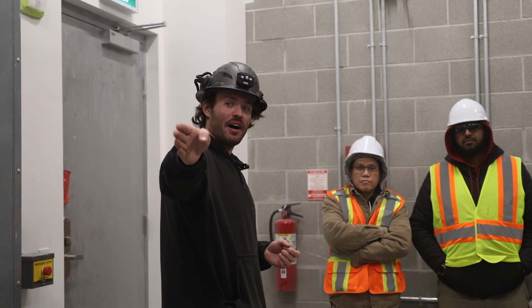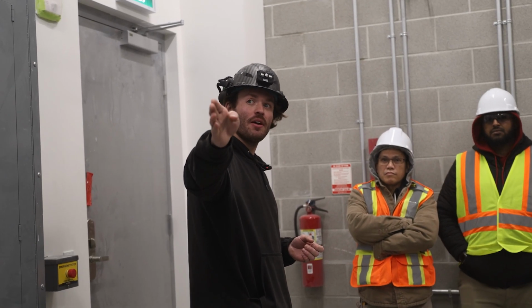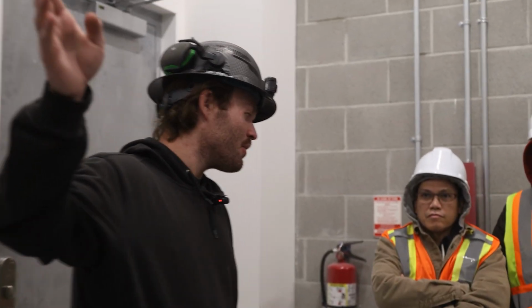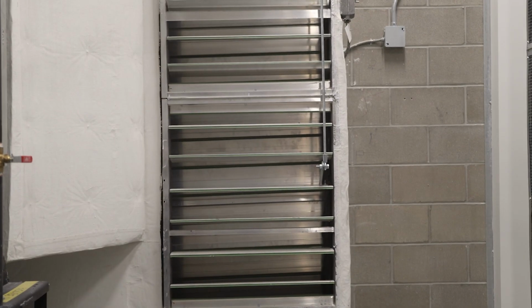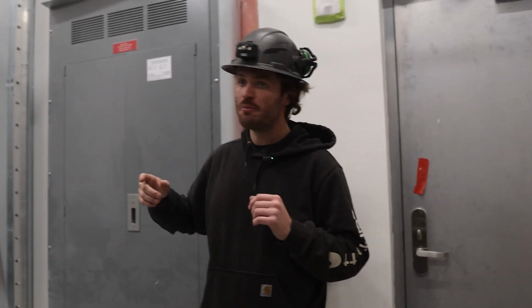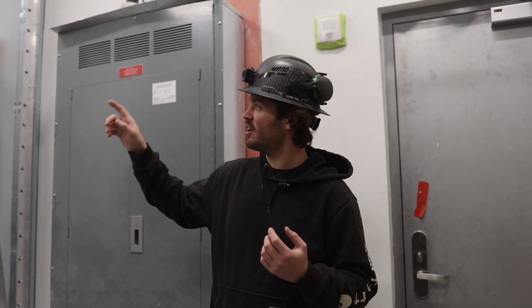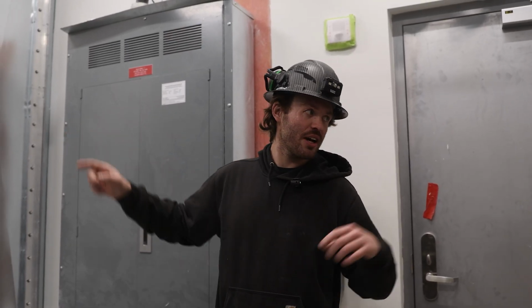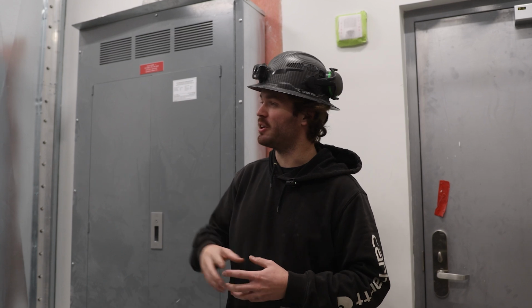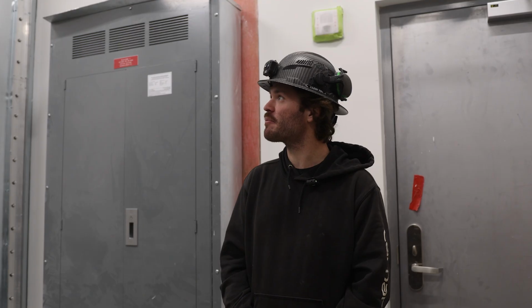The louvers behind the camera guy there, those ones are our recirc louvers. Those will always be open. We need a place for the air to be pushed by the radiator, by our rad fan, to go on startup. So recirc it back to the room. But as temperature starts to increase in here, it will open the louvers to the outside, push the hot air out, and these guys will begin to close. Just always need air. Whether it's coming into the room or going out of the room, it's required. Otherwise, this thing's going to get hot and it's not going to be happy.